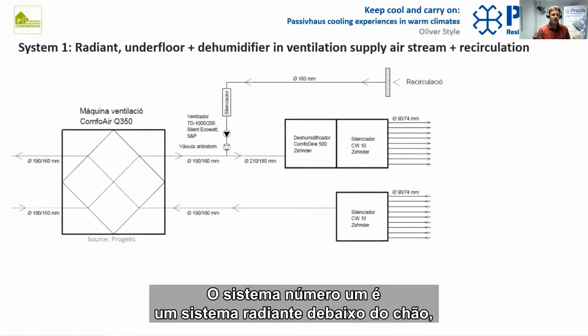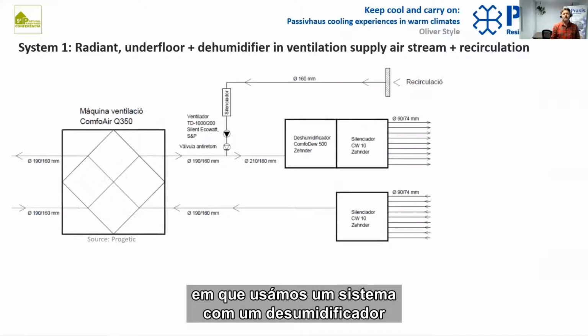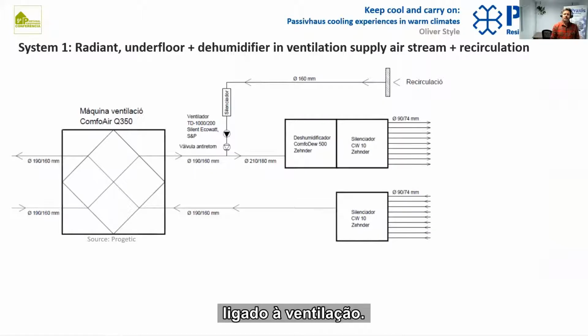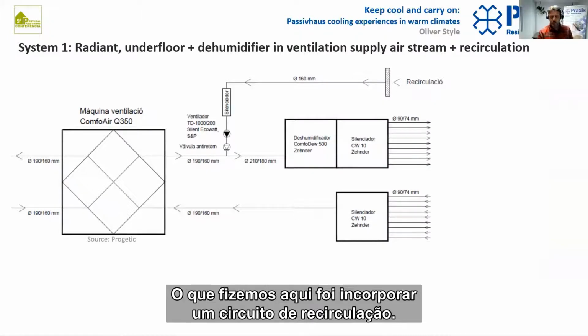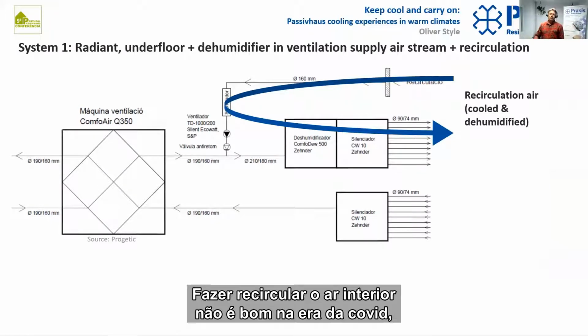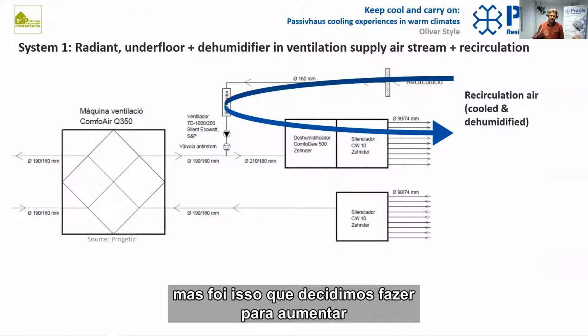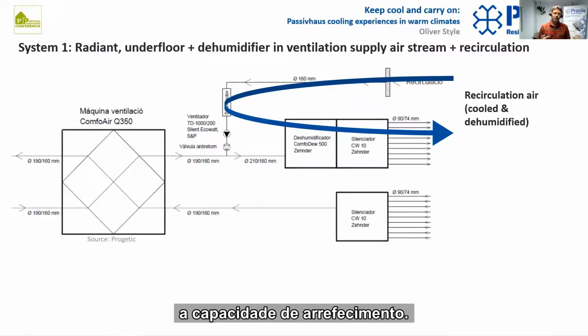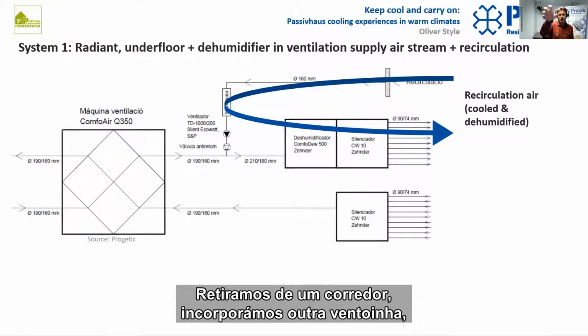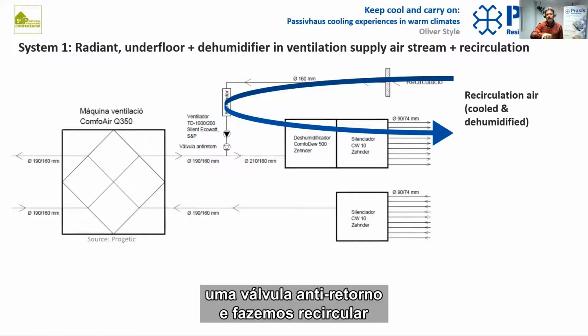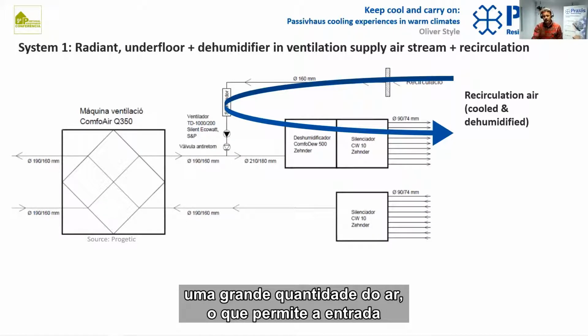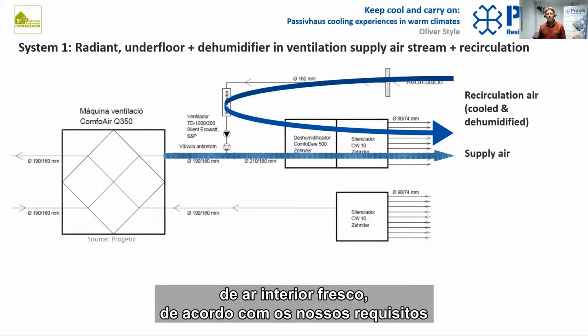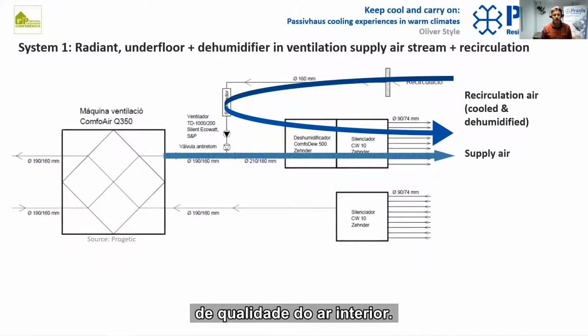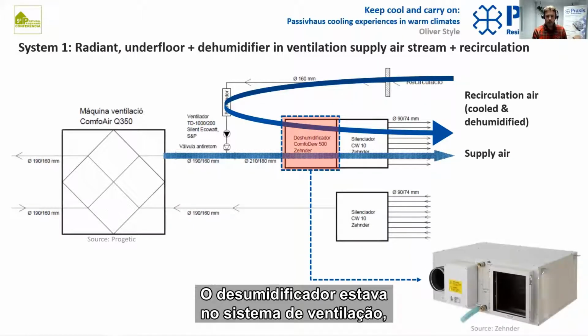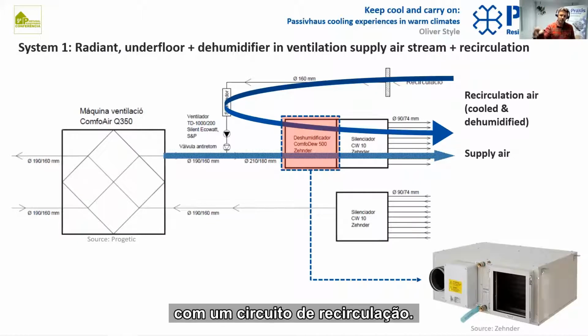So system number 1, this is a radiant underfloor cooling system where we used an underfloor system with a dehumidifier in the ventilation supply airstream. What we did here was incorporate a recirculation loop. Recirculating indoor air obviously is not a good thing to do in times of COVID, but this is what we decided to do to increase the latent and sensible cooling power, by taking air from a corridor, incorporating another fan, a non-return valve, and then recirculating a large part of the air and allowing fresh outdoor air to come in just for indoor air quality requirements.